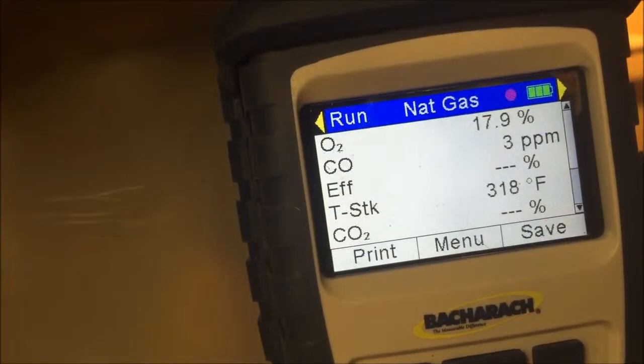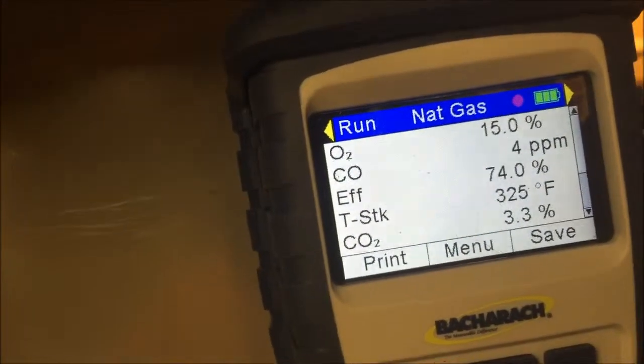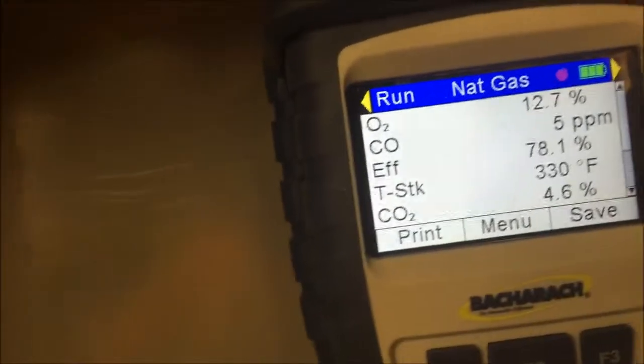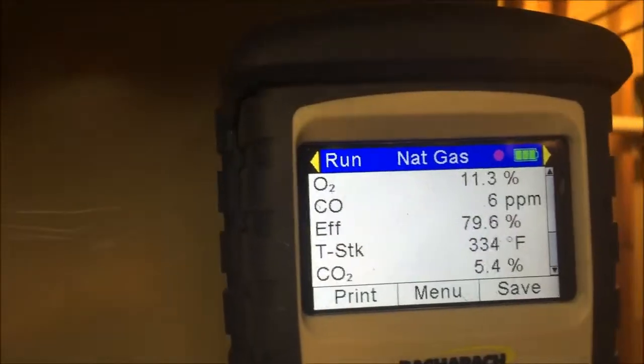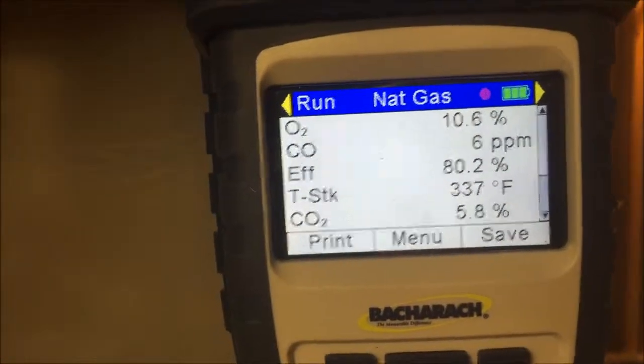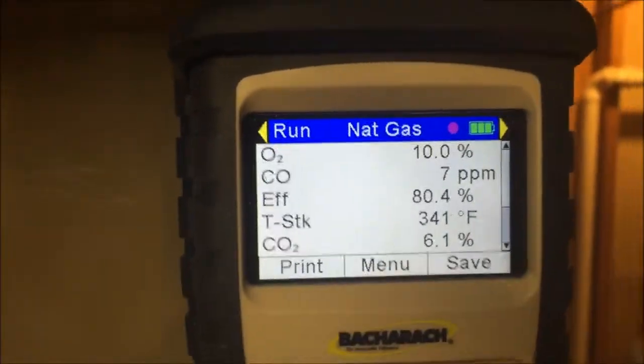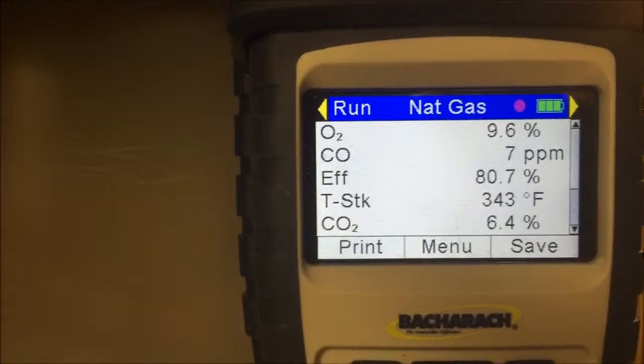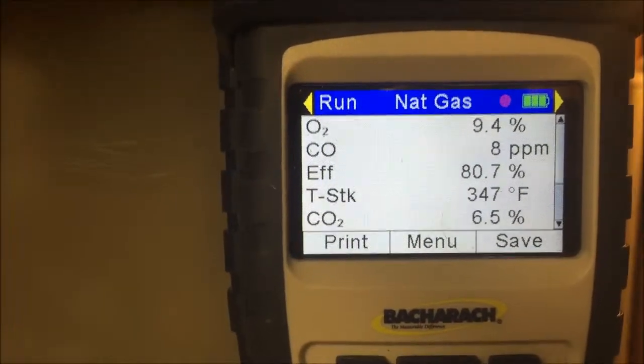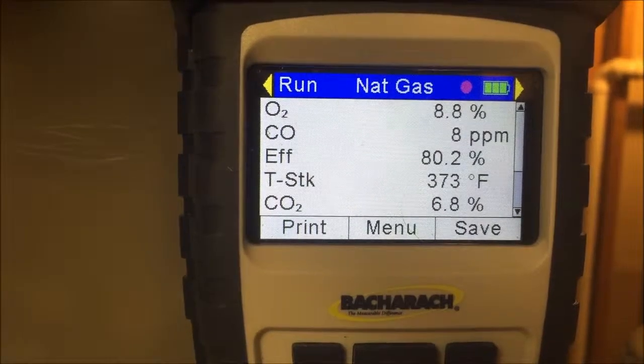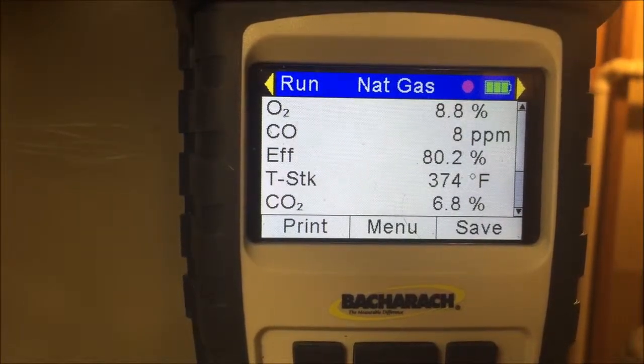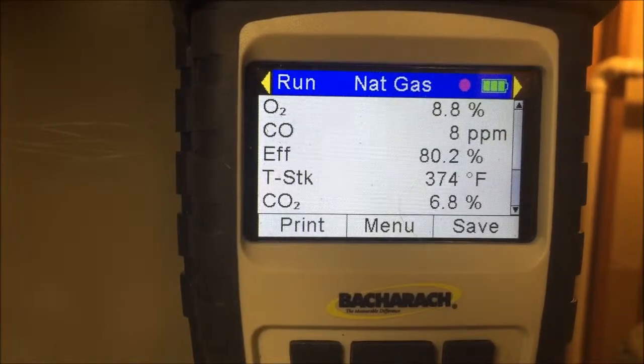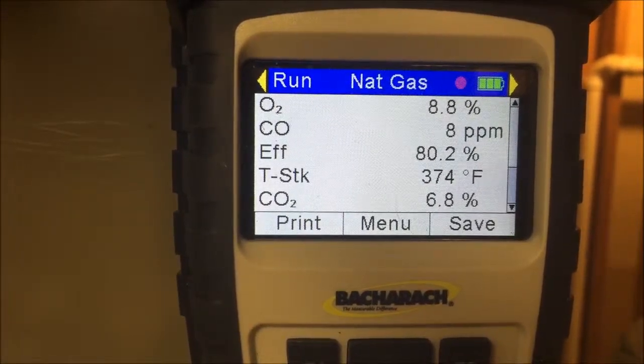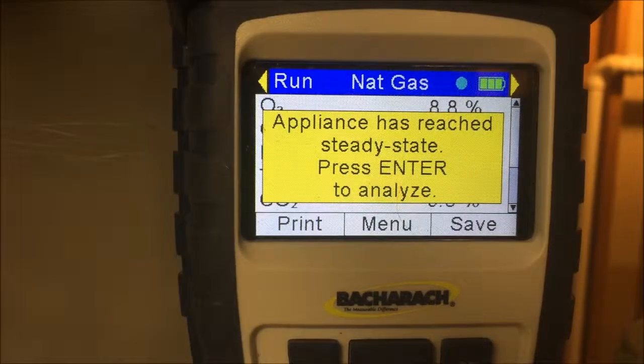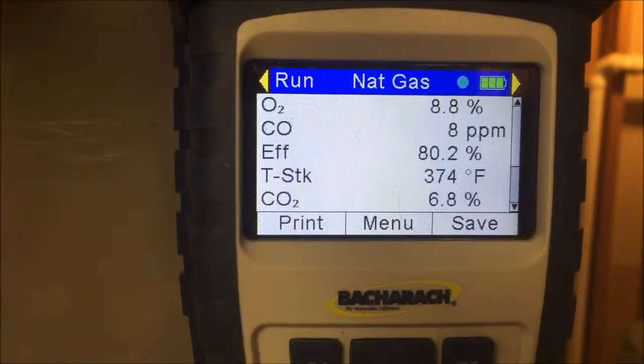Alright, now we're going to change it. I'm going to push that probe back in where it belongs. Right there. We'll let that stuff stabilize. Look at those numbers going down now. Put it on high fire. We increase the gas pressure to 3.5. It should stabilize any moment now. The numbers are really settling down. There we go. Turn blue.